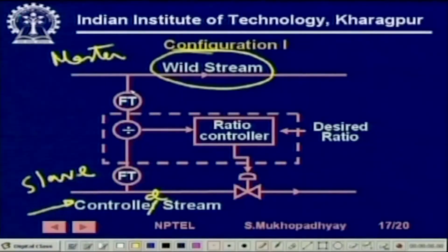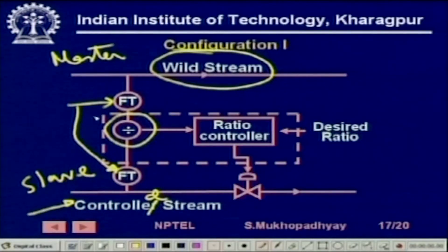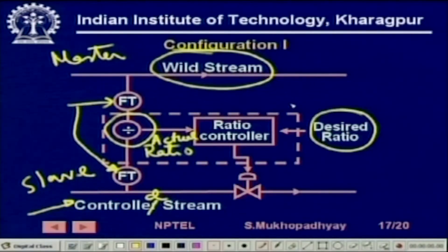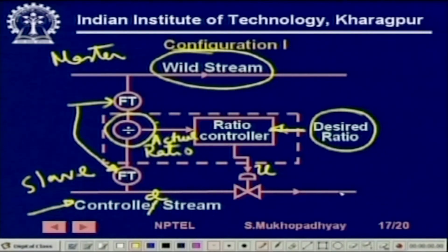Obviously, to be able to reach that we have to measure the streams, so we are putting two flow transmitters which actually measure the volumetric flow rates. Here we are dividing them to get the ratio — this is the actual ratio — and this is the desired ratio. This is the ratio controller, which gives its input to the valve so that the controlled stream is increased or decreased such that this ratio is maintained.